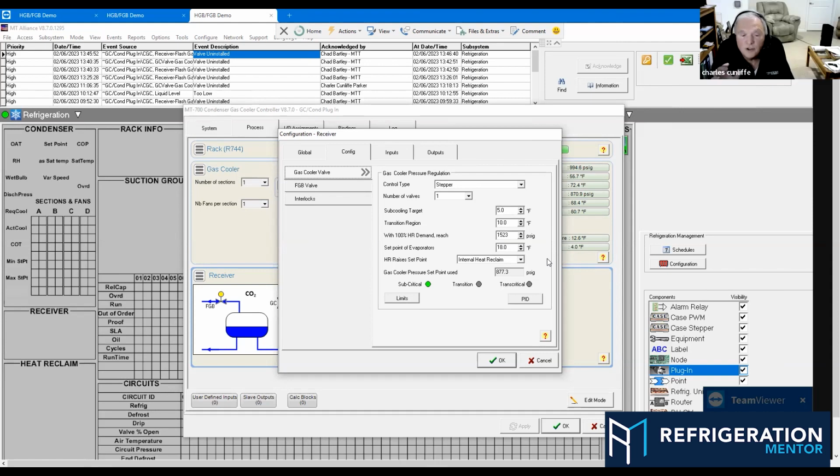Yeah, your targets are going to be the actual temperature. I'd have to see how he set this up, either drop leg or drop leg conditions for the CO2, and the pressure and temperature, right? So we want to keep it away from the saturation at that point. We want to keep the temperature lower, but we want to keep the pressure higher in that flash tank to make sure that the CO2 is going to be 100% liquid at that point.